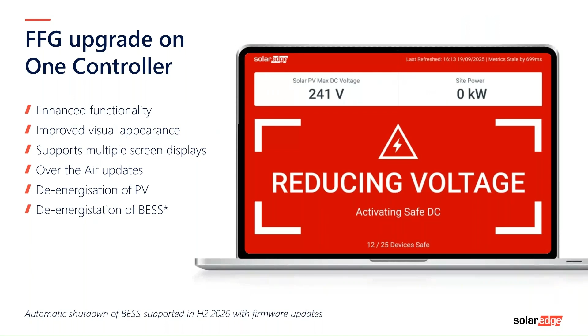The next one is the solar PV system safe screen, and for this particular site we've got 10 volts, but as I said, you would normally have probably in real terms 30 volts per string, and that's the value you'd get here. Normally the inverter runs at 750 volts. When you turn the inverter off with safe DC or with the Firefighter feature activated, it will give you probably around 30 volts is the value I would expect.